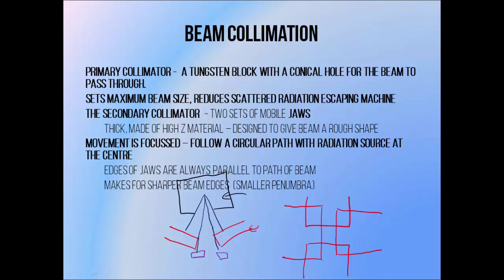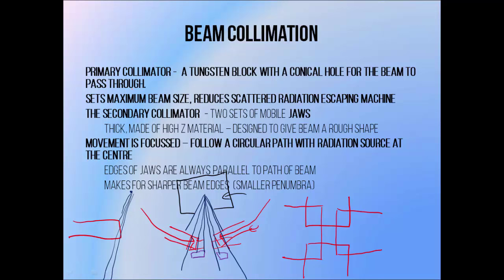The jaw movement is said to be focused, meaning they move in a circular path such that their edge is always parallel to the path of the beam. This helps to keep the beam edge nice and sharp, since if the jaws followed a flat non-focused path their edges wouldn't be parallel to the beam's direction of travel, and some photons would travel further through the jaw than others. This means that the face of the jaw would not block the beam off cleanly, and photons that travel only a short distance through the jaw would contribute dose to the edge of the field, resulting in a wider beam edge. We often call this region the penumbra, so a focused jaw allows for a narrow beam penumbra.